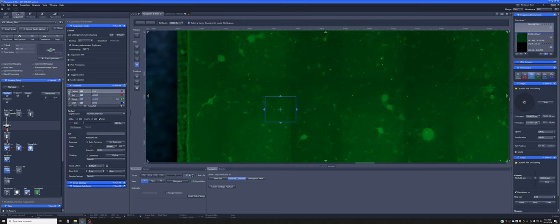So the way you do that is you load settings that have been optimized by the MSL staff to help you do this. They are in the list near the bottom. There are ones that say WF, that stands for wide field. There are a set that said WF image and WF map. The ones you want to use, if you're trying to make quick maps are the map subsection and which ones you use depend on whether you want to do maps using bright field, fluorescence and bright field, or just fluorescence. So for example, if we just bring up the one that's just fluorescence, you'll see that it has four possible channels: Cy5, a red fluorophore, a green fluorophore, and DAPI. You don't need to use all of them. You can just turn off the ones you don't want.